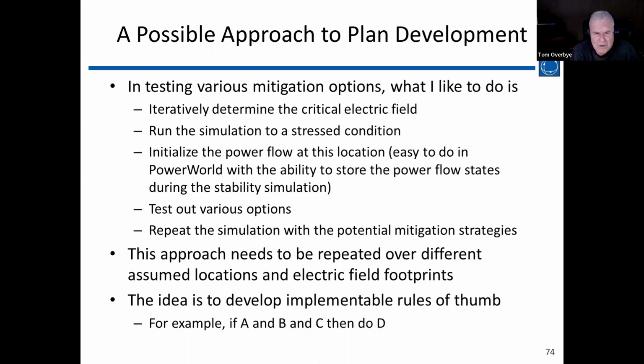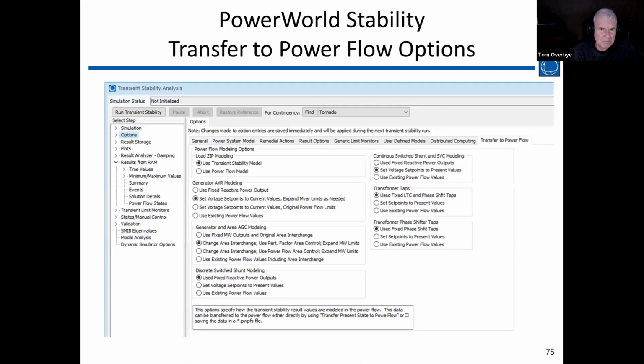That might be, for example, if A, B, and C have occurred, then do D. A might be that HEMP has occurred, B might be the voltage at this bus is below 0.75 per unit, and you might not have a C, and you'd just shed that unit. Or you might have A, HEMP has occurred, B is the frequency is above 60 hertz, C is that generator isn't too heavily loaded and has a lot of GICs on its transformer. Then we might open up that transformer and associated generator.